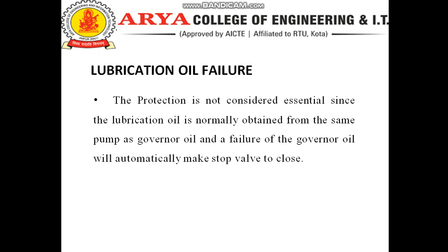Now in this slide we discuss the lubrication oil failure. This protection is not considered essential, since the lubrication oil is normally obtained from the same pump as the governor oil, and a failure of the governor oil will automatically make the stop valve close.